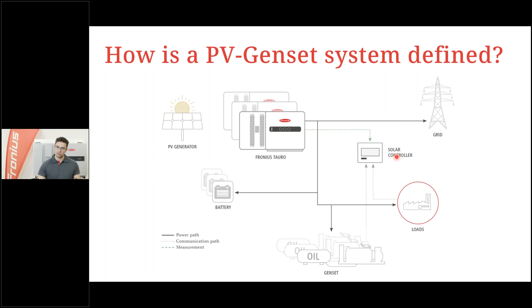Because imagine we have no grid, the load is very low currently, but it's a very sunny day and we produce a lot of energy. And if the batteries, which are optional, are full, where do we go with the surplus energy if the grid is not there? It's a very simple solution. We need to regulate the inverter output power down, and this is done by our partners from DEIF, for example. So the solar controller is a very important tool in this concept.